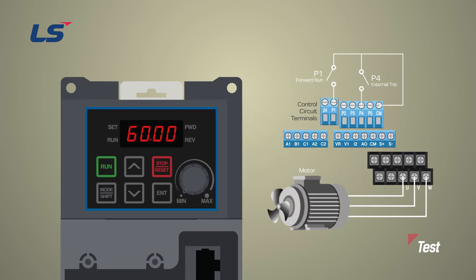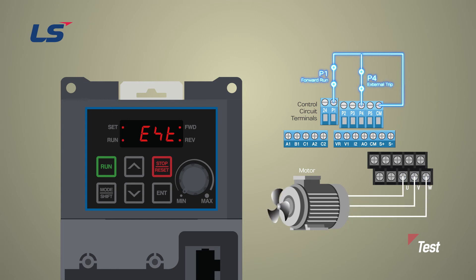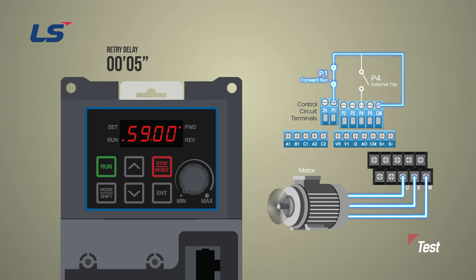We will proceed with the test under the parameter conditions set earlier. First, turn on the P1 terminal to operate the motor. Make a trip condition by turning on the P4 terminal. When the trip message appears on the LCD keypad and the motor stops, open up the P4 terminal from its closed state. Since external trip is a latch-type trip, the trip is not canceled even if P4 terminal is opened or turned off. It automatically resets 5 seconds after the trip occurs, and the motor starts because the P1 terminal is on.